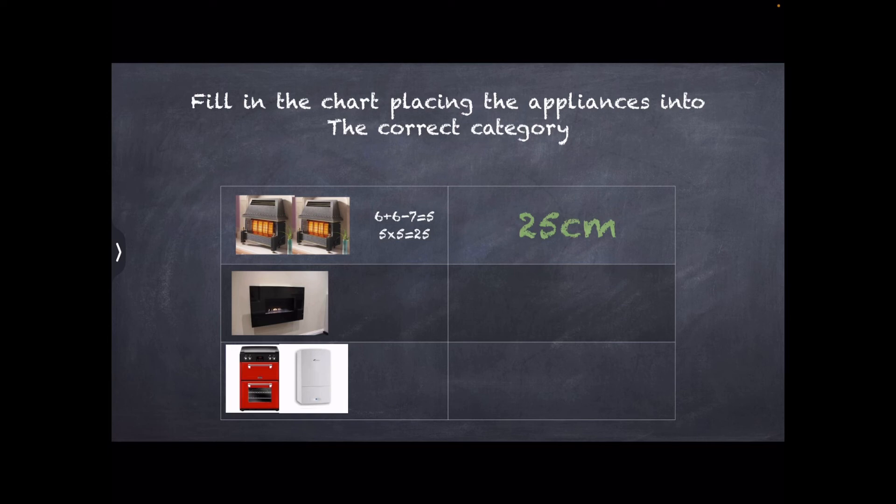So for the flueless space heater, you simply use the flueless chart. And that would tell you that a 3.7 kilowatt fire in a 30 meter squared room requires 155 centimeters squared of ventilation.